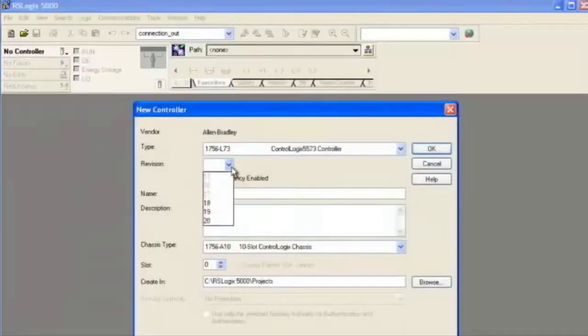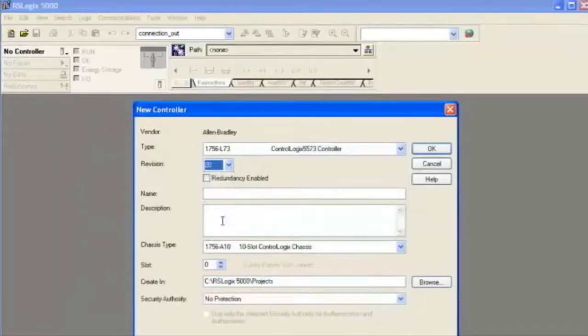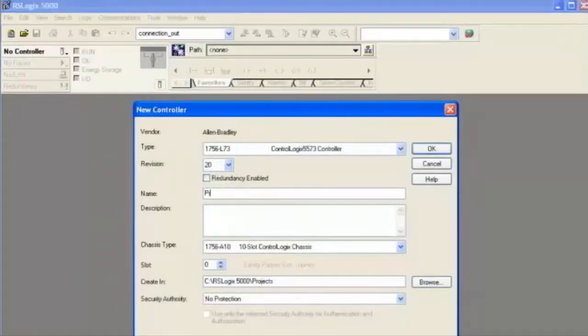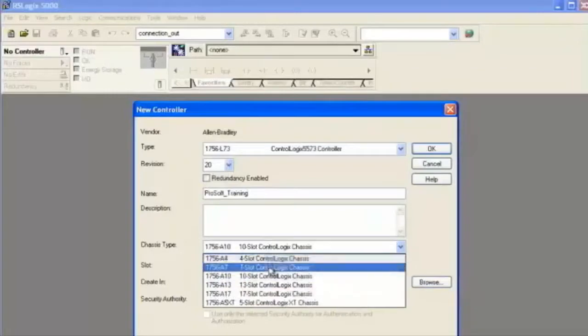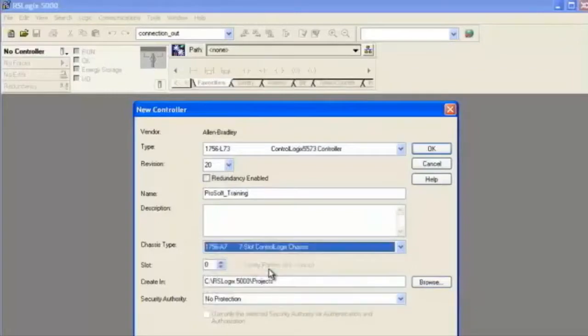Now we're going to configure an I/O connection to a ControlLogix processor version 20 or newer. We'll choose version 20 and give it the name of ProSoft Training. I have a seven slot chassis. We'll select OK and go down to the 1756 back plane.